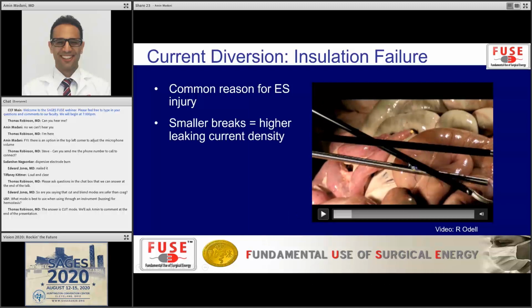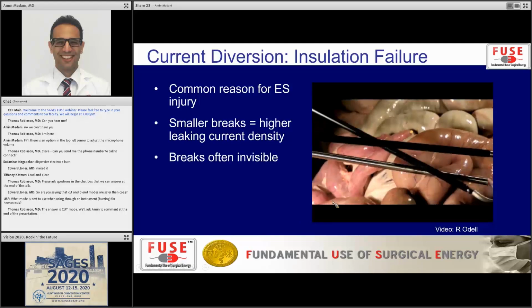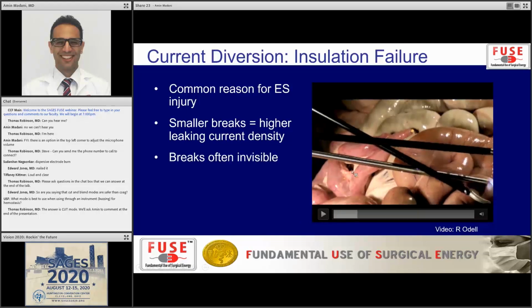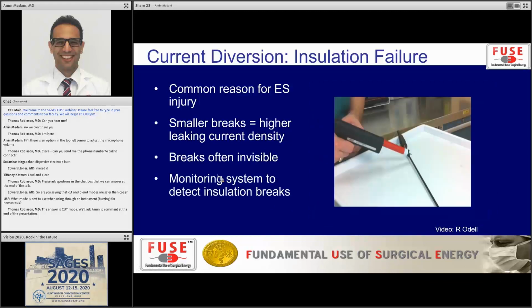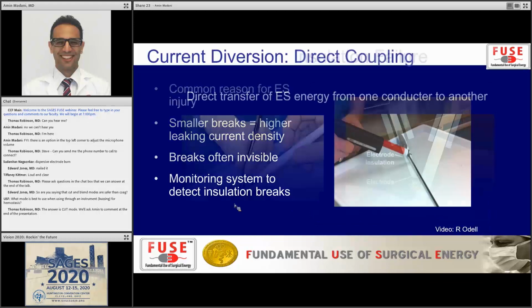The smaller the break in the insulation, the higher the current density, because it's a smaller surface area of contact. Often these small breaks are not visible to the naked eye, so these are particularly problematic, and we have monitoring systems to figure that out for us.